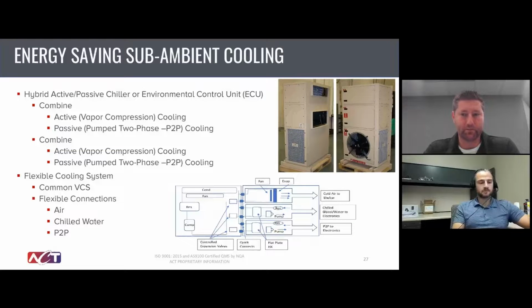For the applications or times of the day when the outside air temperature is sufficient to cool your inside space, so cooler than your inside space needs to be, we turn the compressor off and circulate the refrigerant with a pump instead. So it just becomes a pumped liquid loop. We pump the fluid through a heat exchanger that you blow air across, then that fluid picks up the heat and dissipates it to outside air.